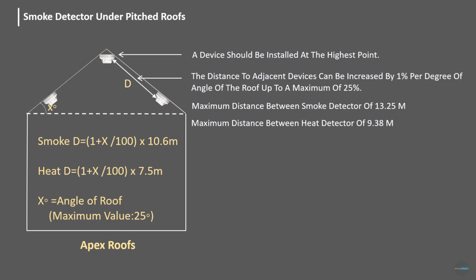Friends, in an apex roof, the distance between detectors depends on the roof angle. For smoke detectors, distance D equals (1 + x/100) multiplied by 10.6 meters. And for heat detectors, distance D equals (1 + x/100) multiplied by 7.5 meters. Here x is the angle of the roof, but the maximum angle x to consider is 25 degrees. Let's see some examples.